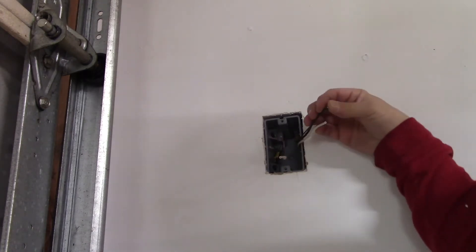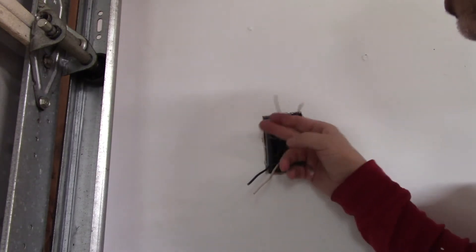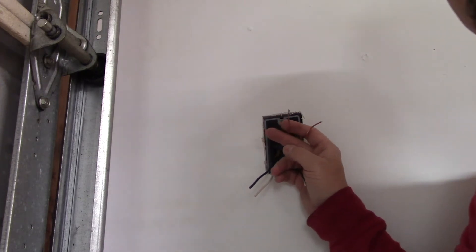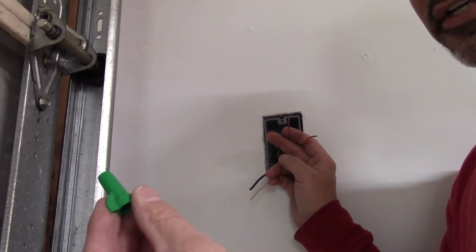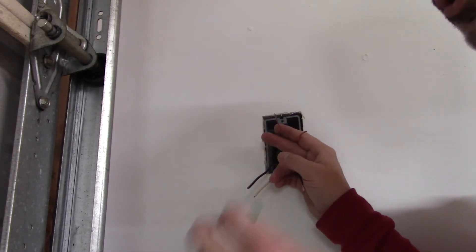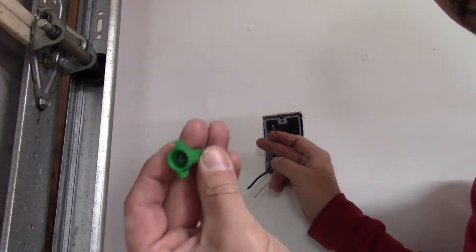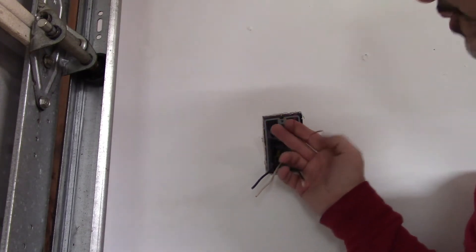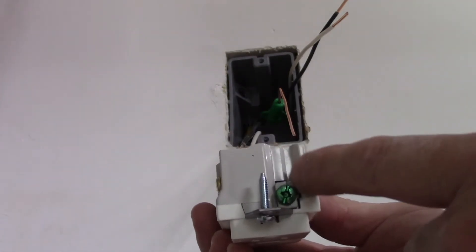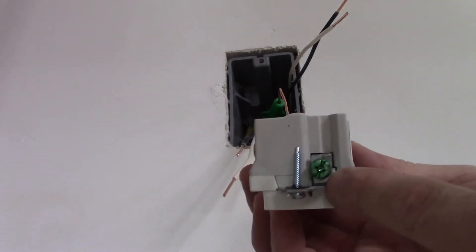So I need to tie these two bare wires together and connect just one of them to the outlet. You should not just take the ground wires and twist them together. There should be some kind of mechanical device holding them together. You can get these green wire nuts that has a hole in the end of it. You can feed one of the wires all the way through it, and then stick the other one in the big end where the threads are. Twist it together and that's a mechanical connection for the ground wires.